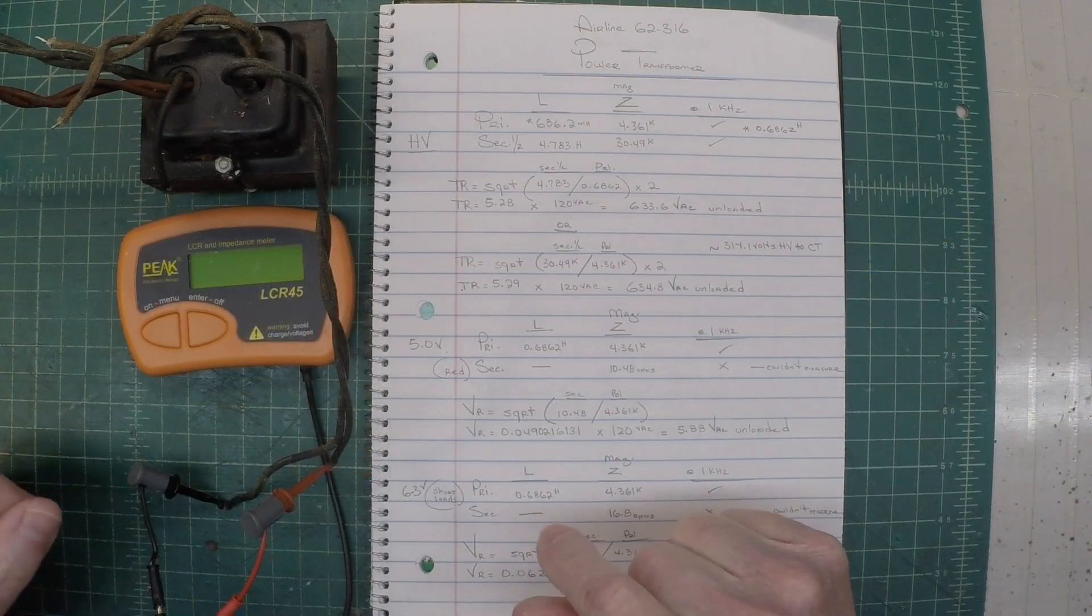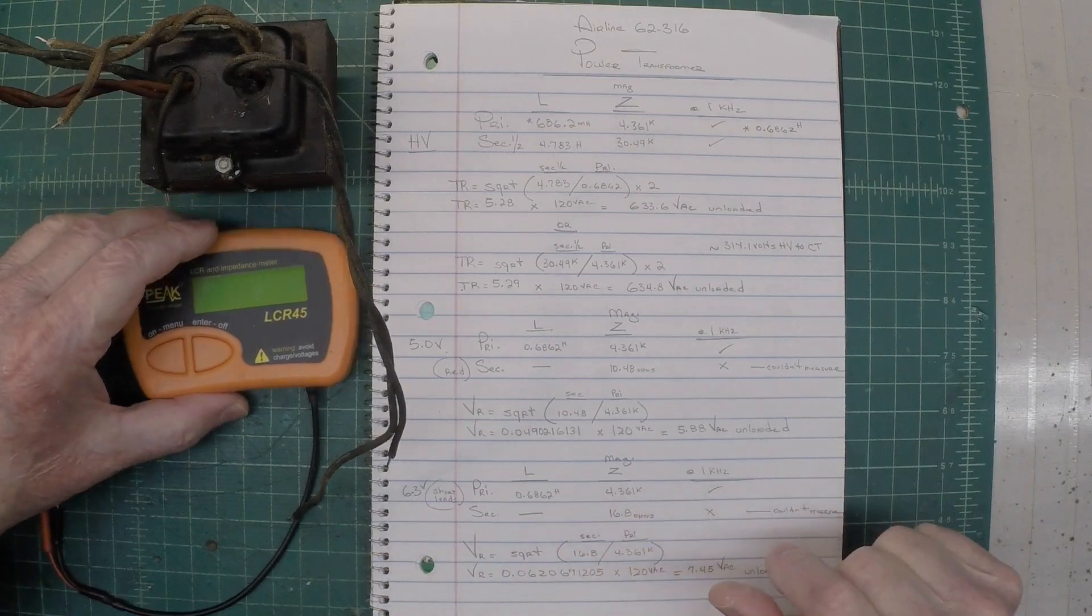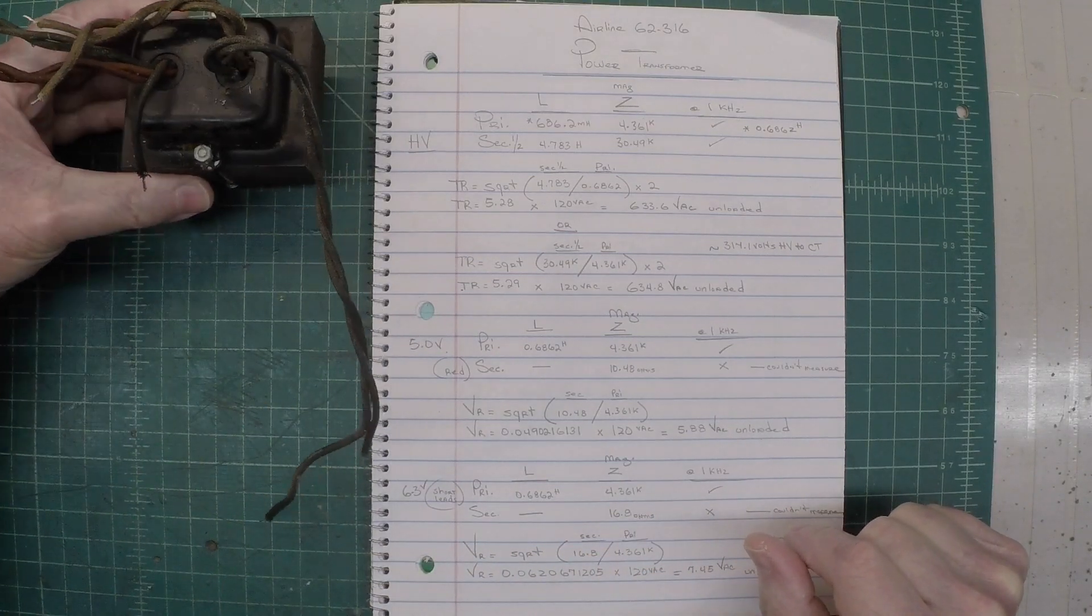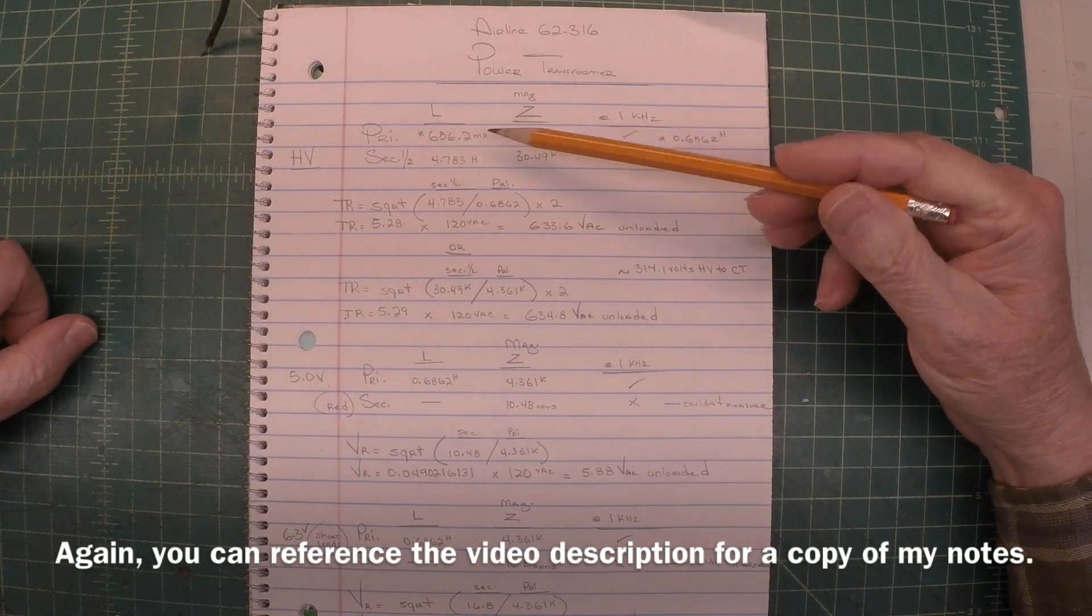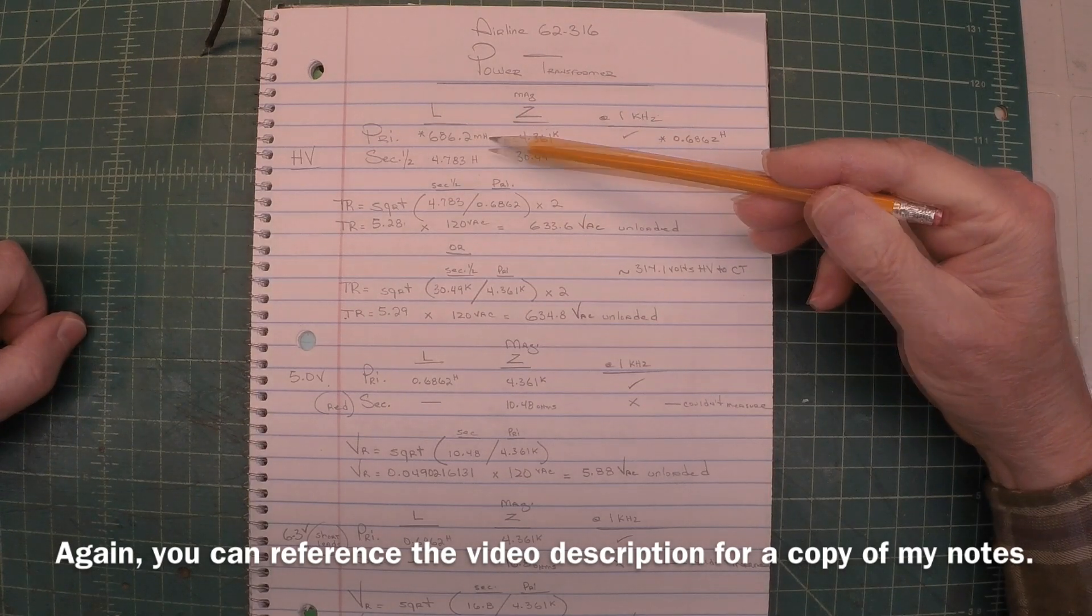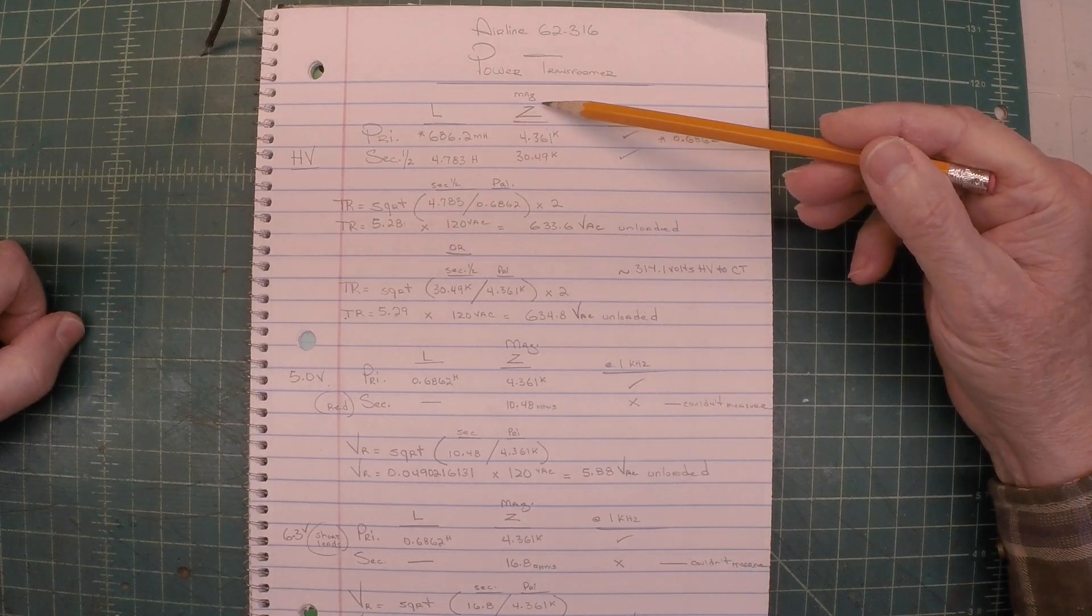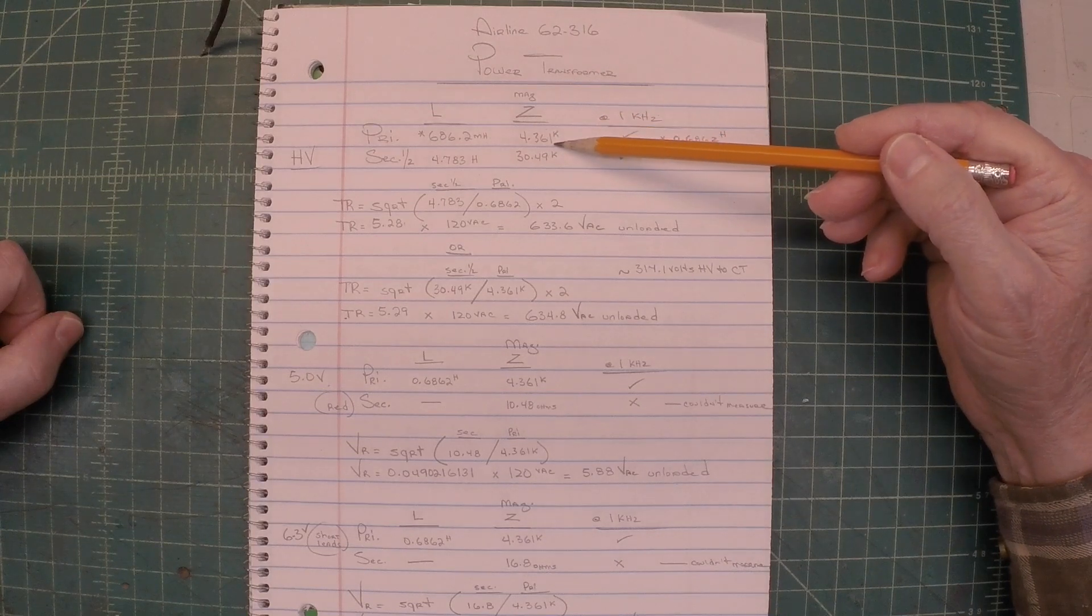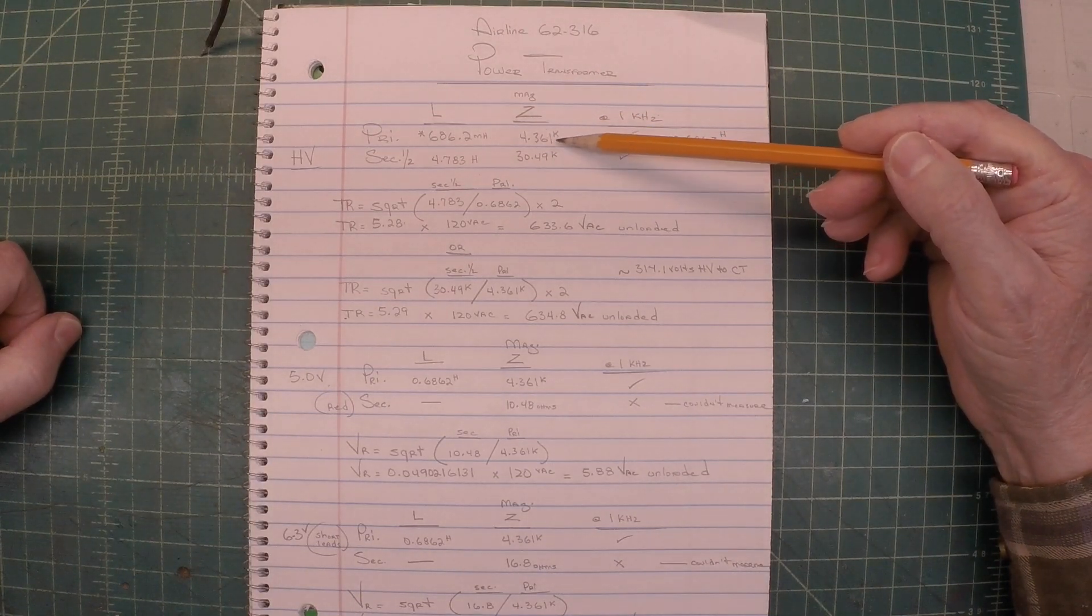So I've recorded the magnitude of impedance for the primary and secondary windings. Let me unhook the LCR meter and just get this off to the side. And let's look at these calculations a little closer here. Using the data that I captured this morning, you can see the primary inductance called out and the secondary inductance. And the magnitude of the impedance is indicated for the primary and secondary.